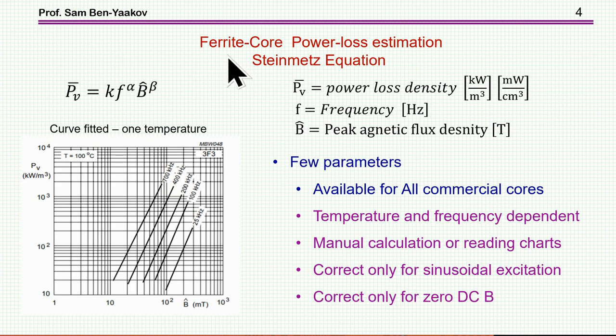So let me start with the losses in a ferrite core, ferrite material. It has been found that the losses can be expressed by this equation, the so-called Steinmetz equation, who was first to suggest this template. So here we have the losses in terms of kilowatt per meter cube or milliwatt per centimeter cube. F is frequency, while sometimes it's in kilohertz, really depends on the constant here. And B is the peak magnetic flux density in Tesla. So this is a very well-known template, which is now used very widely by manufacturers of ferrite material.